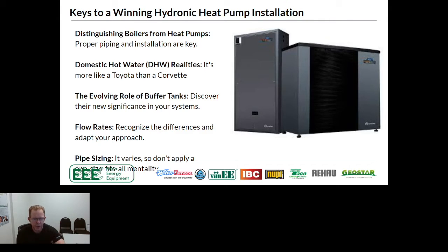Maybe we're replacing igniters sooner than we should be, having to service the boiler more frequently. If you don't put a buffer tank on a hydronic heat pump, it can be as bad as killing the compressor. So we really, really want to pay attention to the buffer tank and understand what it does.